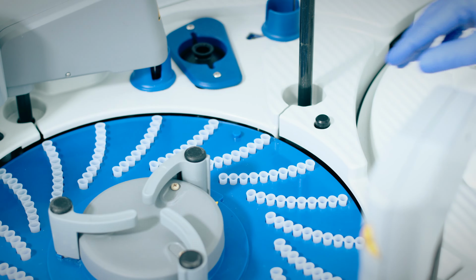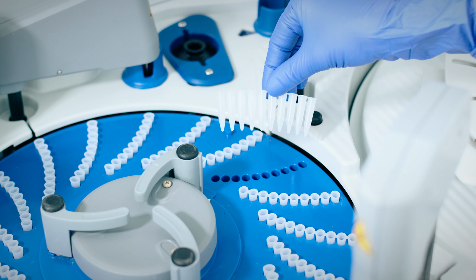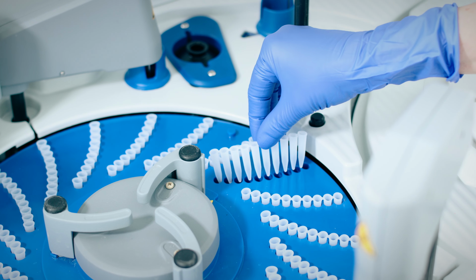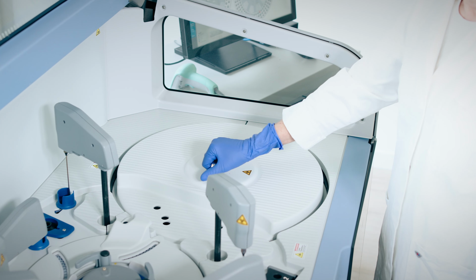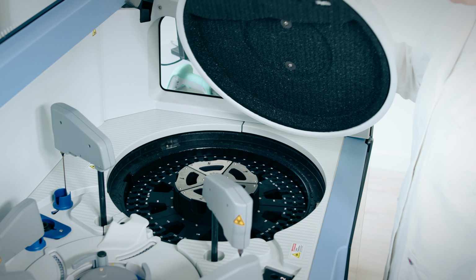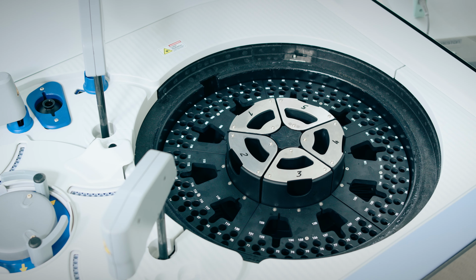The reaction rotor is heated to 37 degrees Celsius and it houses 20 different arcs which are comprised of 10 individual cuvettes. On the right-hand side of the top deck, we have the reagent rotor. It is cooled to 3 to 9 degrees Celsius and features 150 positions for our allergens, also known as capture reagents, and our common reagents. For easy loading and mass storage, it features removable wedges. This is the fluo bead position. It has a built-in vortexer and can hold 2 fluo bead tubes.